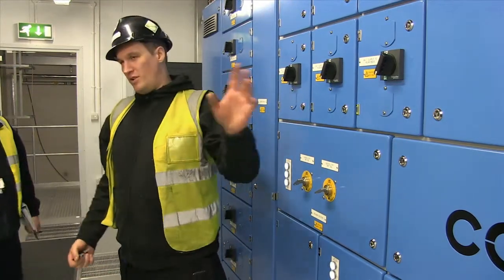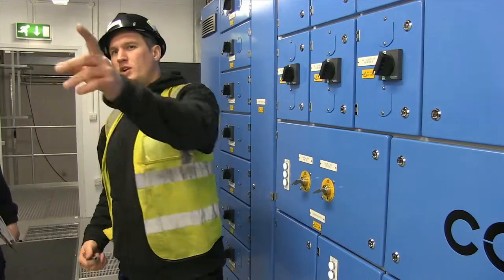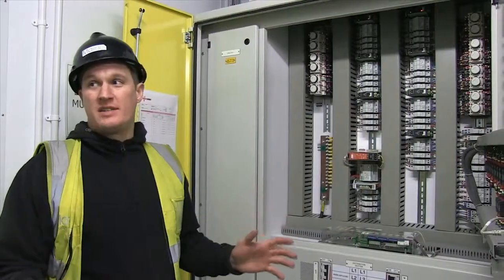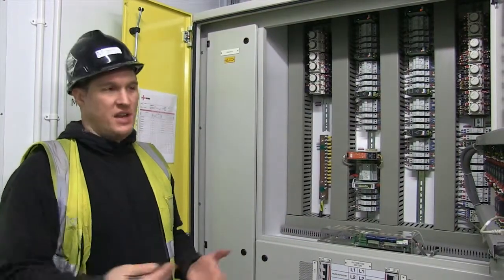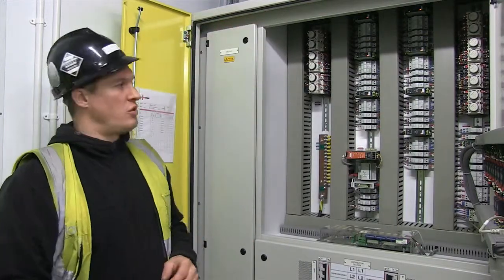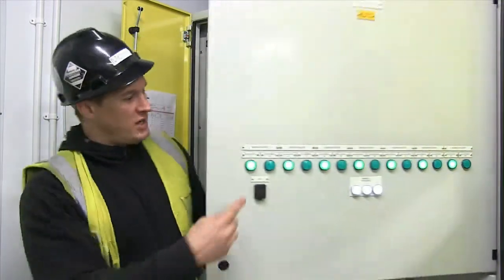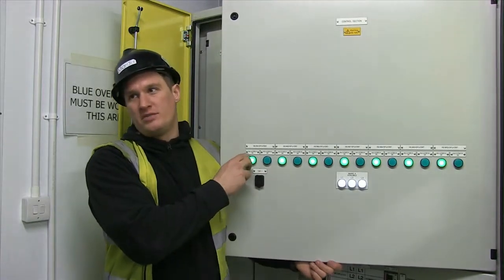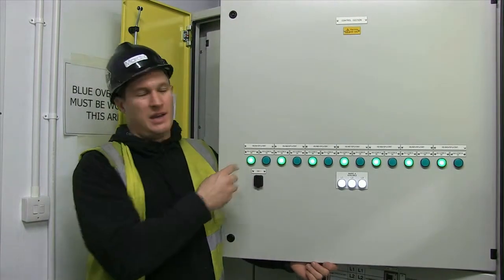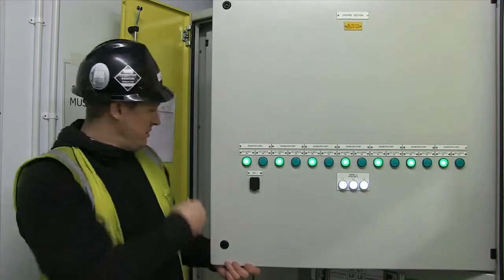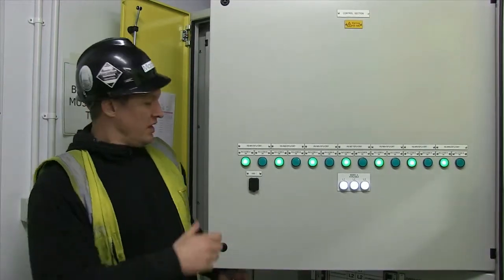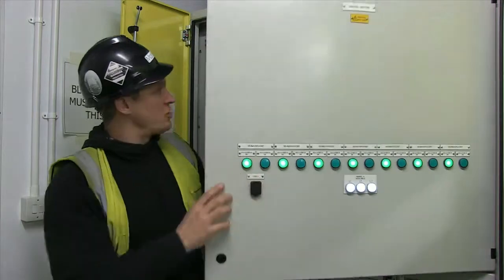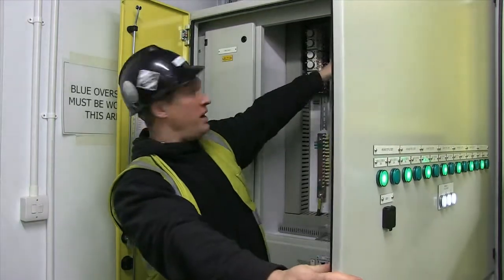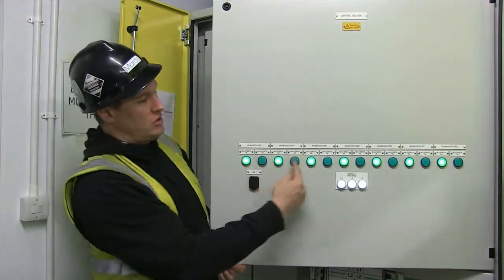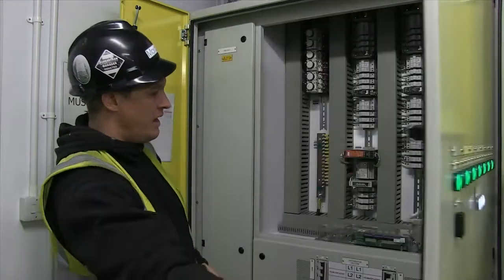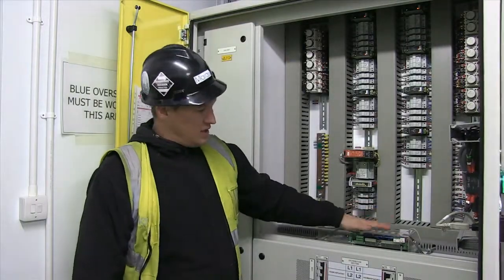UPS system. Obviously, Socomec are going to go through the UPS system. We're just going to have a look at the critical panel. The panel is exactly the same as the central panel, other than the way that it's fed. So this one is fed from that mechanical UPS in the corner. So although it will change over supplies, it won't actually see a loss of supply because it's fed from a UPS, so it shouldn't ever change over. But if you wanted to manually kill it, put it all into B stream yourself, literally just kill the supply there. All the contactors will just, phase failures will drop it, contactors will close, and it will just toggle across to the B stream.